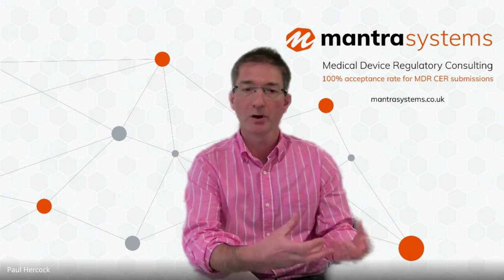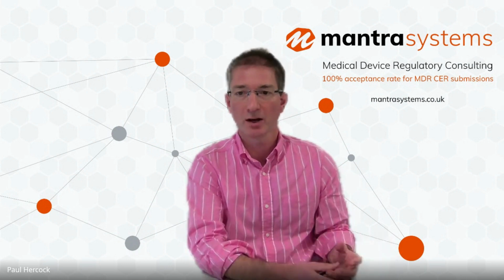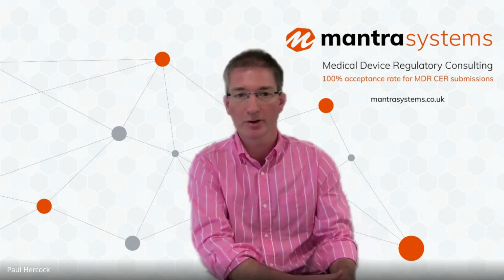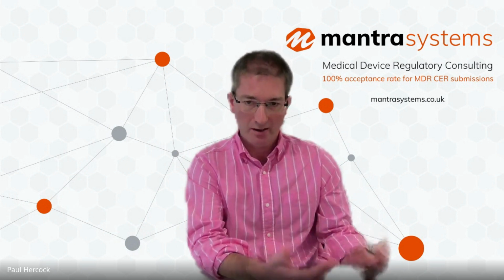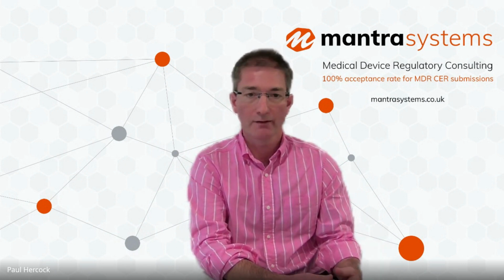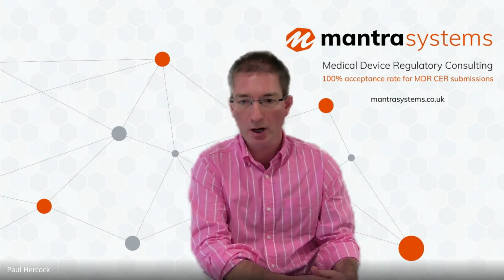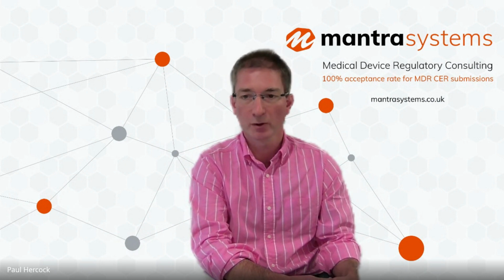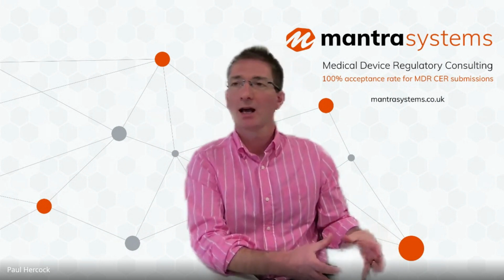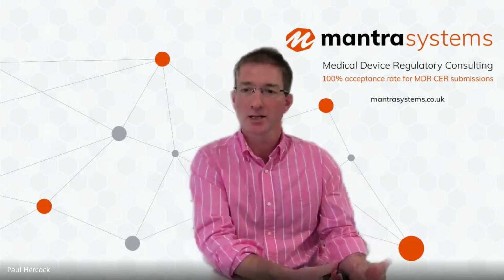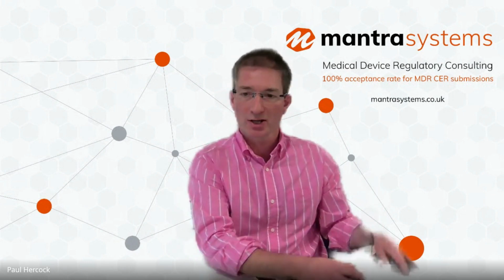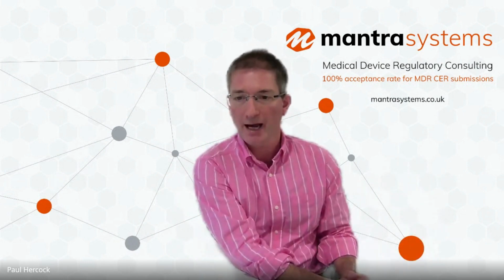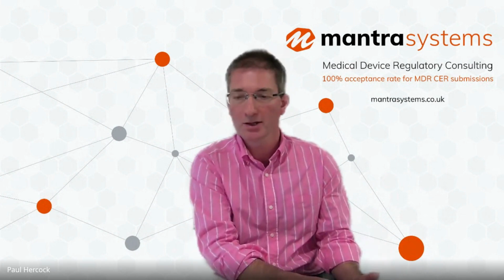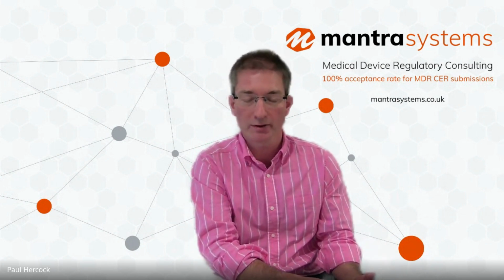So if you've got data in the state of the art that you wish you could use for your device, the first question is, is that device equivalent? If the answer is no, then technically speaking, you can't use it to support conformity. You can't use it as a basis of conformity, but you can use it to kind of round off the circle at the end. But the primary requirement is that you've got data on your device or an equivalent device.